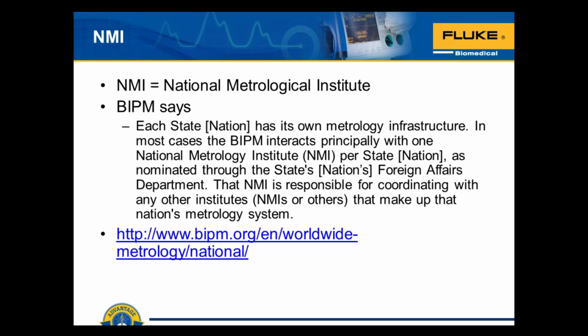So, for example, if you are in Colombia, South America, and you have a DMM, and you need to get it recalibrated, whether or not you send that unit back to Fluke Biomedical for that calibration event, that traceability is going to want to go through that local NMI, especially if you send it locally anywhere. Let's say we had a Fluke Biomedical Authorized Service Center there, which we do, and you send it to that service center. That service center's traceability is through that NMI.